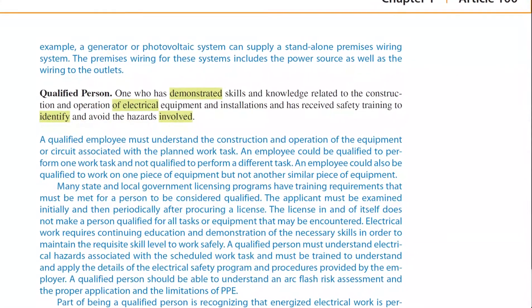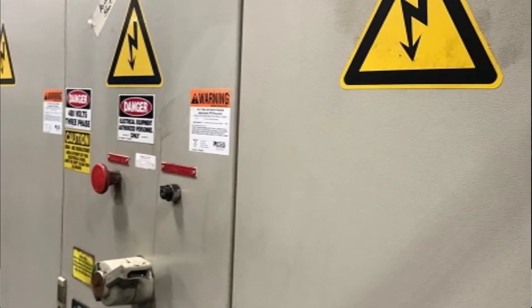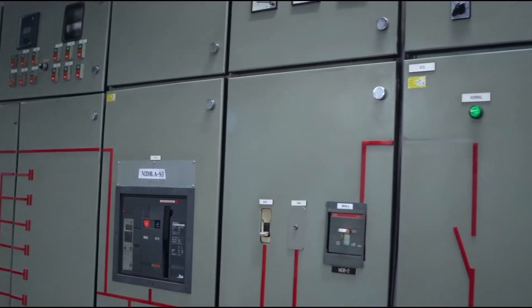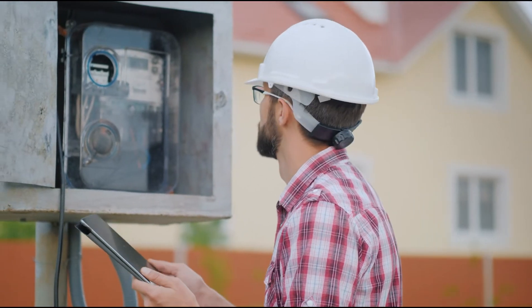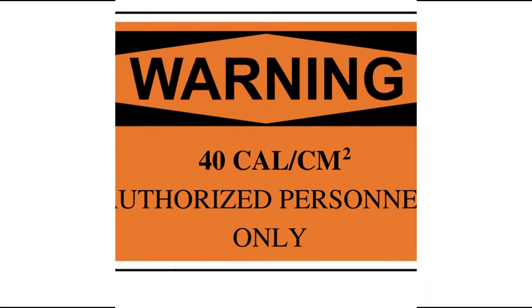A qualified person is defined in NFPA 70E, and part of that definition states the employee is one who has received safety training to identify and avoid the hazards involved. That understanding requires knowing what the different parts of an arc flash label are and what they mean. There are various parts of the arc flash label required by NFPA 70E Article 130.5, as well as specific equipment that must have the label. Equipment requiring labels includes switchboards, panelboards, industrial control panels, meter socket enclosures, and motor control centers in other than dwelling units. Basically, any panel likely to require examination, adjustment, servicing, or maintenance while energized requires a label. If equipment is not likely to be serviced while energized, the label is not required and should not have an arc flash label applied.